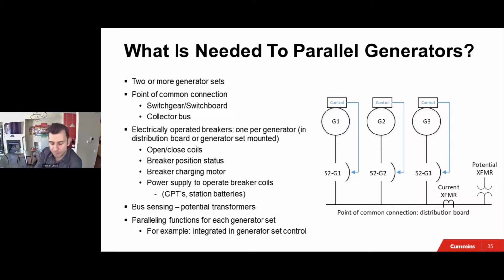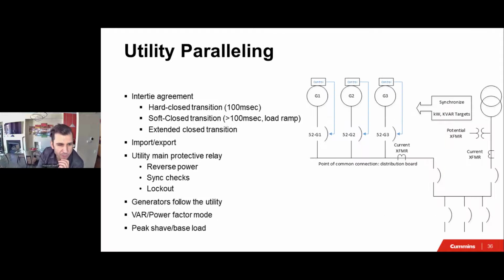And I hope I was able to convey the message to you of the advantage of paralleling gensets using the integrated control. And now I have one slide about utility paralleling, right? Obviously, when you want to parallel with utility, things get more dicey and more complicated. The first thing you want to do is check with the utility. I can't tell you the rules and regulations for every utility. Everyone is different. You may want to have this discussion at least 6 months in advance. Utilities are not thrilled about you doing close transition. Usually, they even charge an arm and a leg to push you away from doing paralleling.